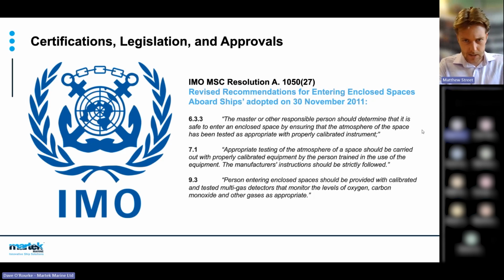Thanks, Dave. And here you can see the thing I was talking about before. I showed you Ben's video, which is from the IMO. It's 13 years old now, but the resolution from November 2011 regarding personal gas detection states: the master or other responsible person should determine that it is safe to enter an enclosed space by ensuring that the atmosphere of the space has been tested as appropriate with properly calibrated instrument.